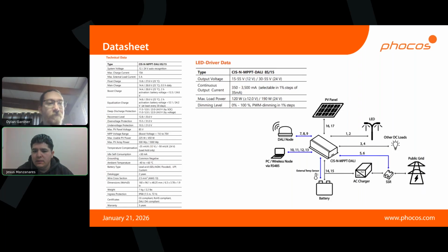Some of the brief features it has: it has the SSR. Our DALI can connect it to an SSR, which is connected to the grid. It sends a signal, turns on the relay on the SSR, allows it to go to the AC charger, and charges the battery. This would be a case where, during the day, if the battery isn't fully charged, the controller recognizes that the battery isn't going to be fully charged by the end of the day, and it turns on the relay. The public grid turns on, goes through the AC charger, and starts charging up the battery, so you have a full battery for the night.